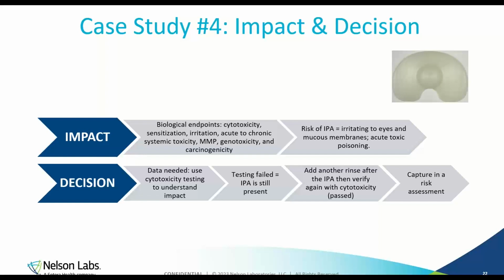So we decided, let's go ahead and do another rinse after the IPA, and see if that gets rid of the residual IPA. The rinse was performed, and we did another cytotoxicity test, and the device now passed. So it's a pretty simple process, but this is a way you can use cytotoxicity to guide a risk assessment. It's a relatively inexpensive and quick test, especially when we're talking about a low risk chemical, where even the residual level on the device was most likely very low. But cytotoxicity testing is so sensitive that we can get a good indicator if further assessment is needed, or if we need to get rid of the IPA rinse and come up with another strategy to reduce bioburden. But this is the process we would go through.